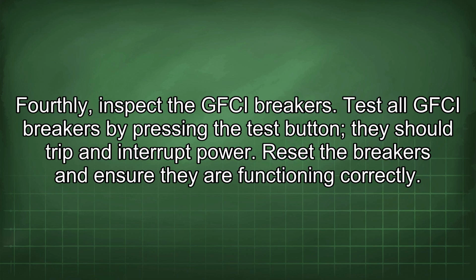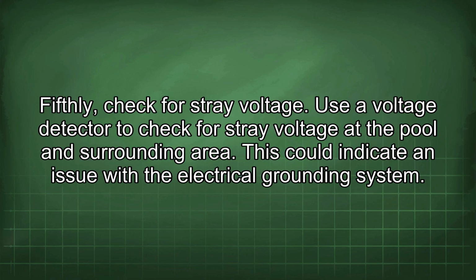Test all GFCI breakers by pressing the test button. They should trip and interrupt power. Reset the breakers and ensure they are functioning correctly. Fifthly, check for stray voltage. Use a voltage detector to check for stray voltage at the pool and surrounding area. This could indicate an issue with the electrical grounding system.